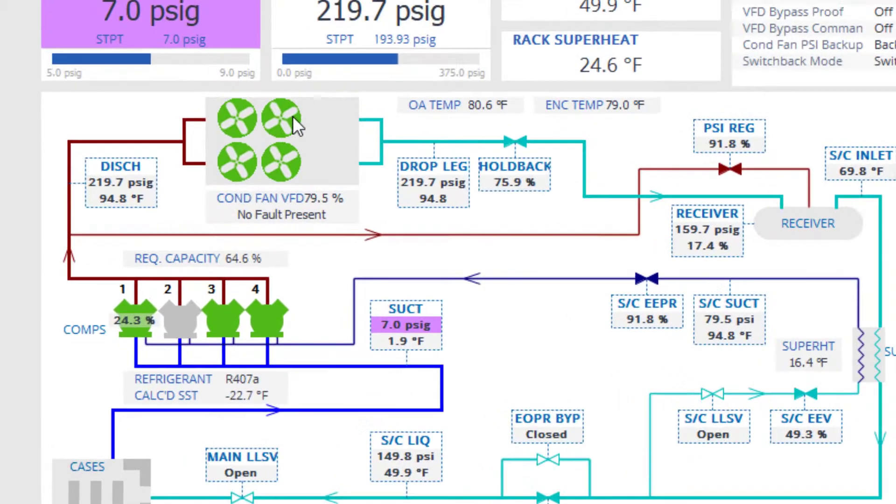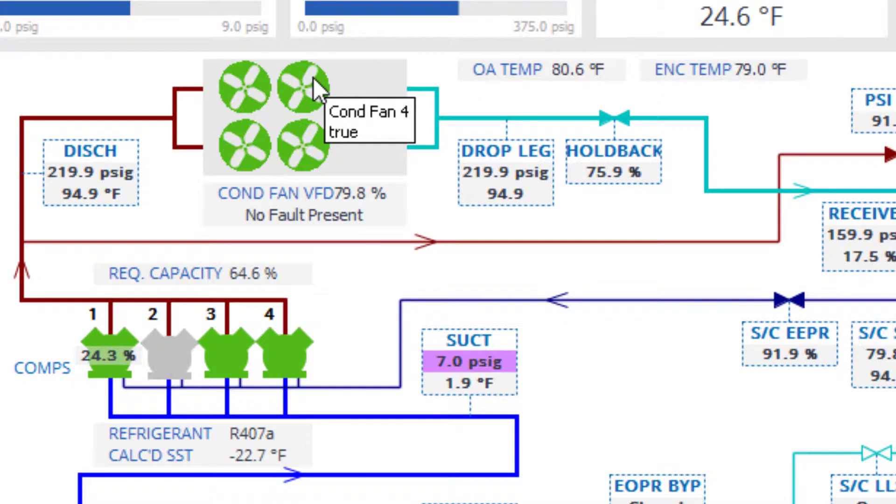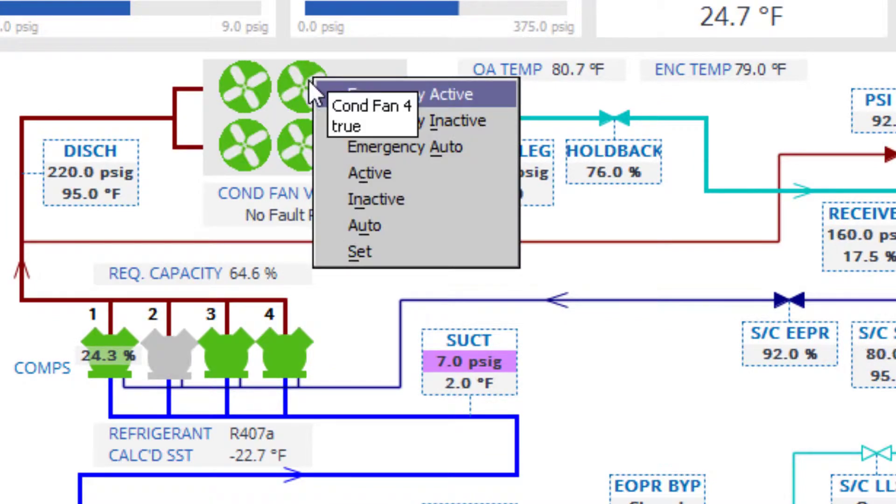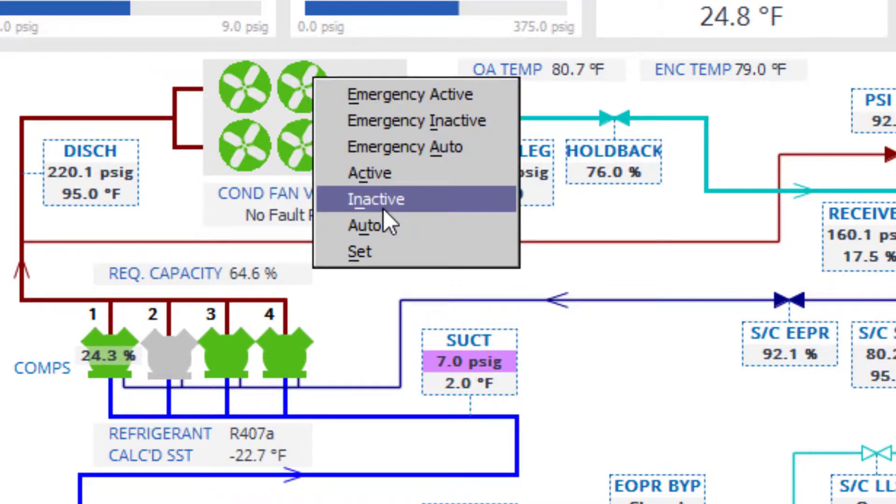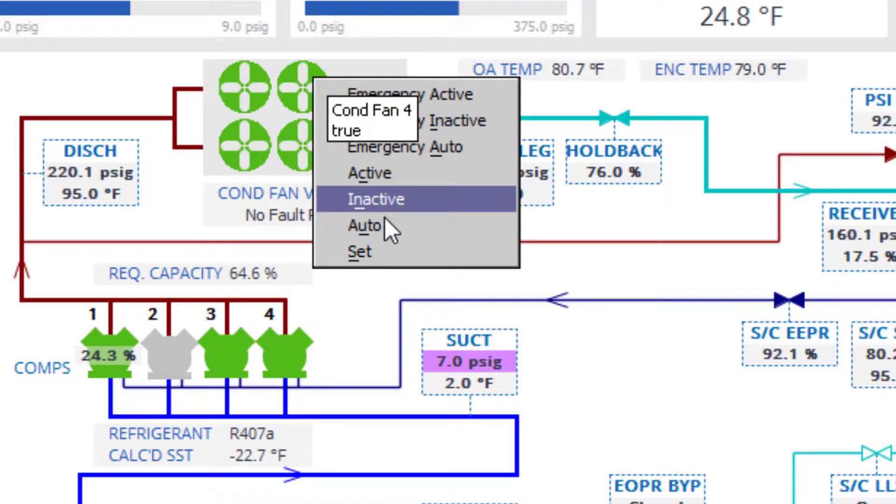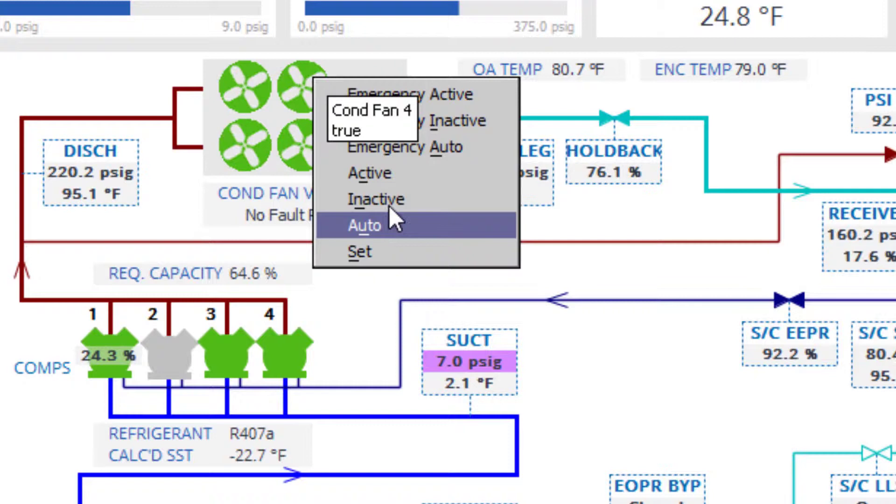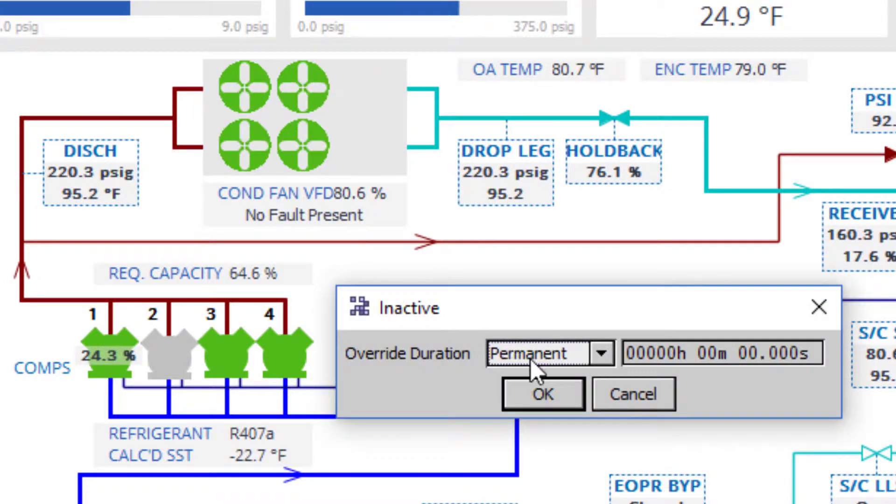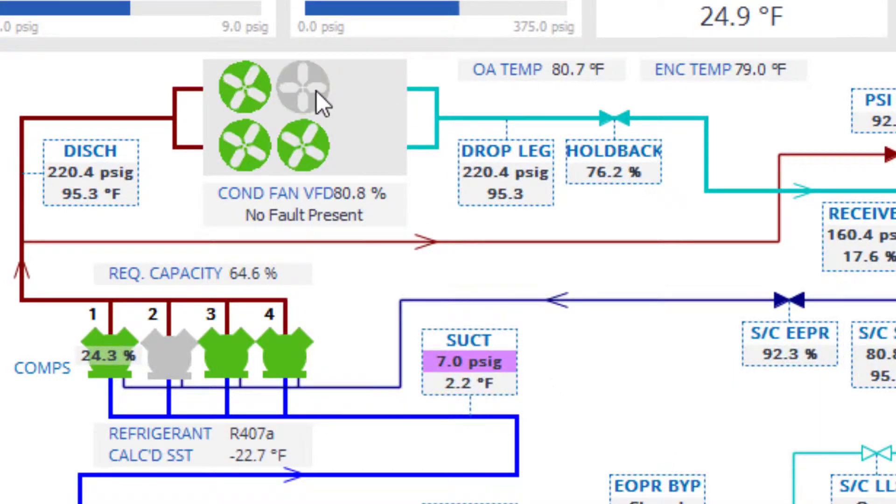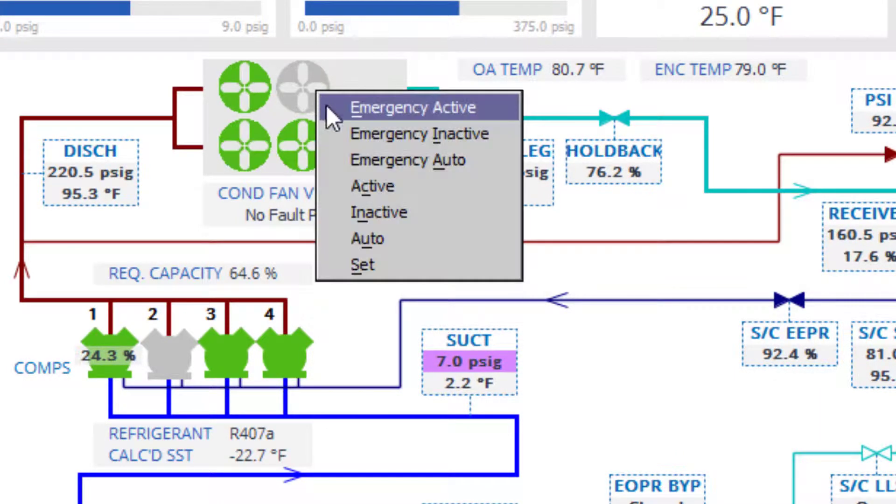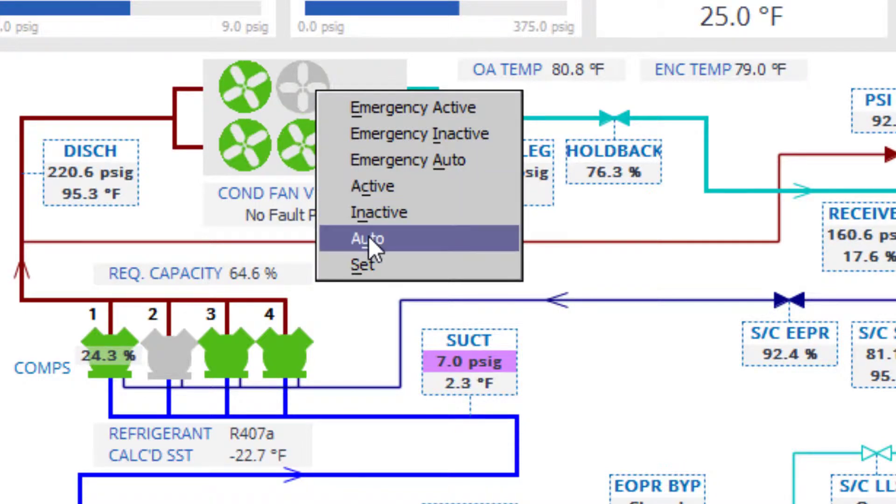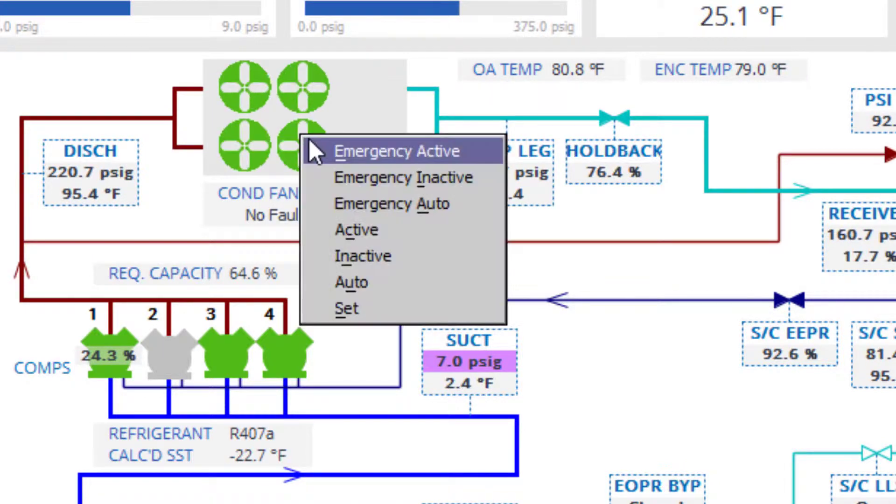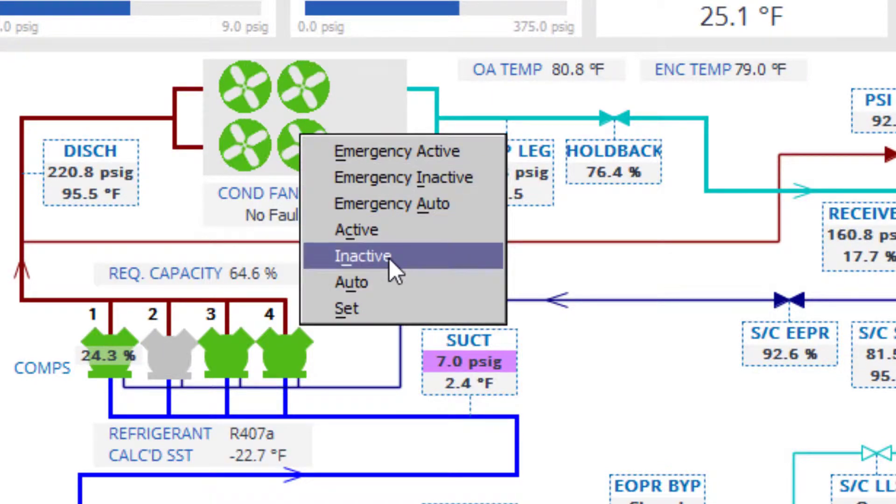For example, right-clicking on the condenser fan icon will allow the user to force the output active or inactive, which will turn that specific fan output on or off. Setting the output point back to auto will allow the system's algorithm to resume control.